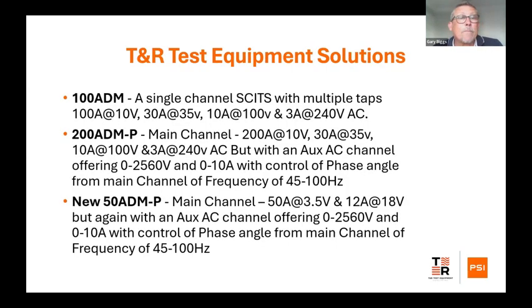What do we offer? Well, we offer these products here, which I won't bore you by going through. We've essentially got three main relay test sets, and these test sets will all test the older mechanical type relays. But the 200 ADM-P and the new 50 ADM-P are a little bit different and have a bit more finer control. So they cross the boundary and are able to test the older higher burden relays, but also some of the more modern digital relays that have very little burden to them.